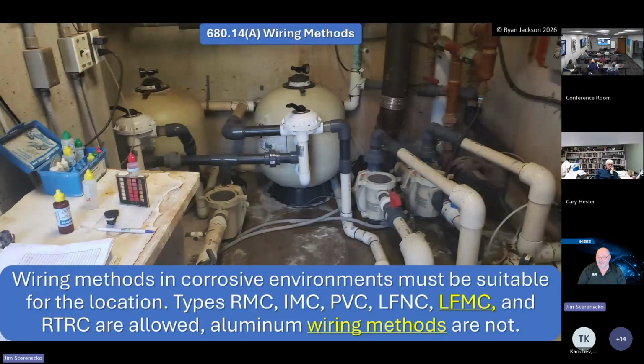When they say that, I think they're talking about, I would have to go back and dig to see if they mean wiring methods like the conductors themselves, or if they just mean the raceways themselves. Aluminum wiring methods are not allowed because they're talking about all raceways in that section. So I'd have to go back and dig. I think you could use aluminum conductors to the panel, but not the equipment ground. But I'd have to go look at it in 680 to actually dig in. And I'll be happy to do that. And I'll get back to Andrew or somebody.